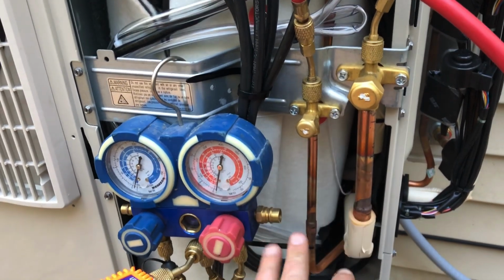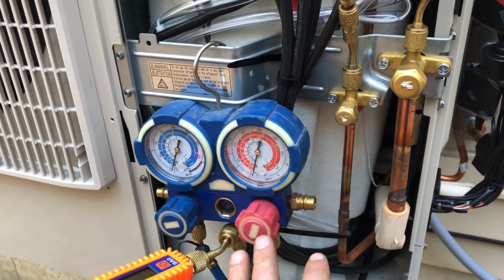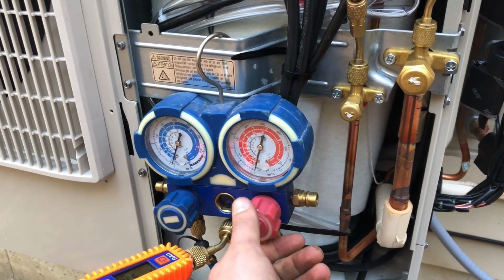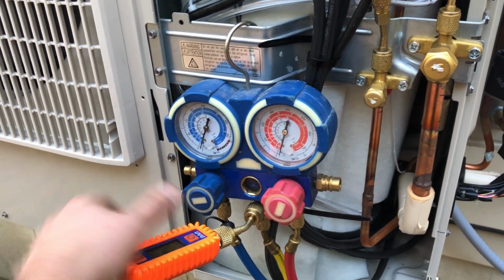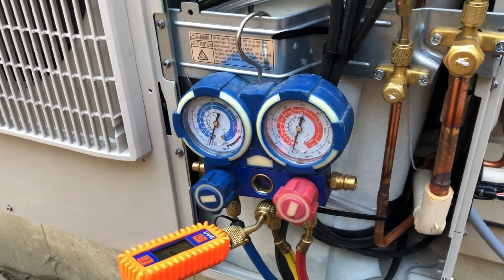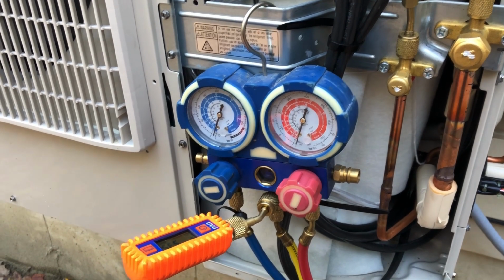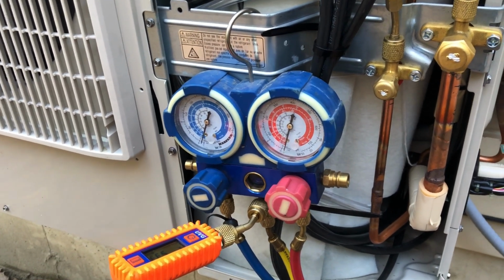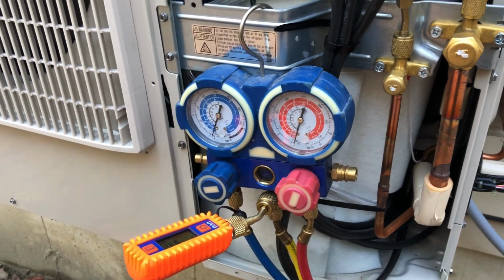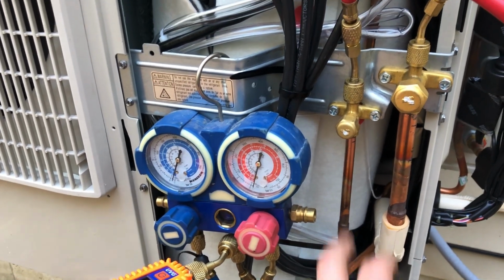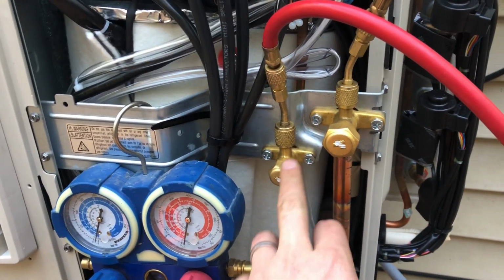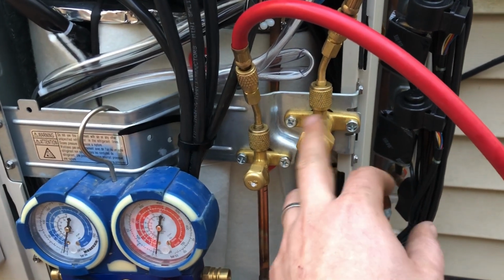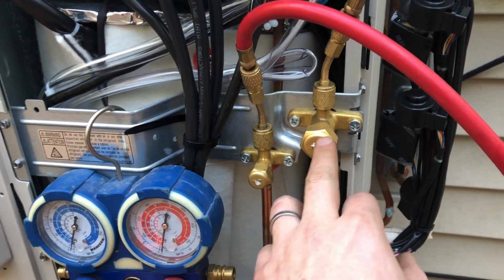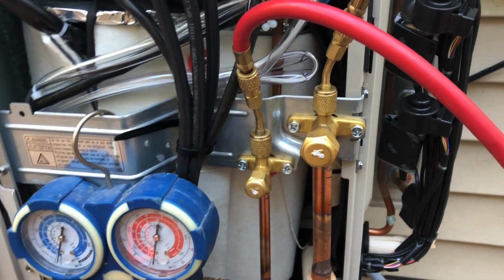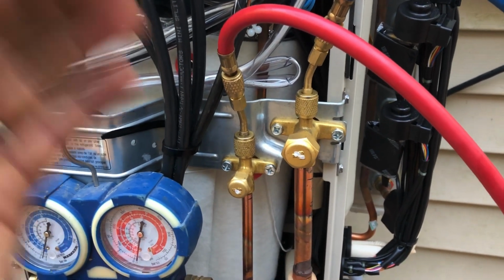All you've got to do at this point is really simple. You're going to close your valves off once you've gotten it to the proper level of vacuum, and your micron gauge is at 500 or below. You're going to close these valves off, and then you're going to open this valve. So you're going to take this nut off, you're going to take this nut off, and in there are going to be two Allen keys. You need to open that, and that's going to send the refrigerant through to all your lines.